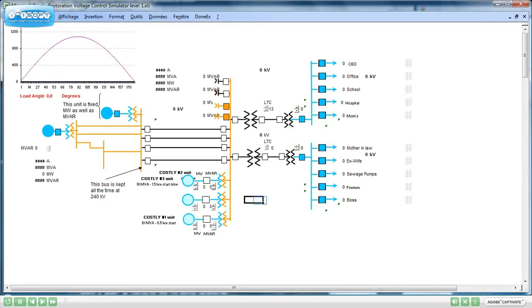The Restoration Voltage Control Simulator asks the user to pick up load with cold load characteristics, to energize long lines with large Ferranti effect, to avoid ferroresonance effects, while keeping the voltage within emergency limits, at all locations and all the time. The simulator checks the user's actions, and if this is not done correctly, it will trip. The users will have to start over again.